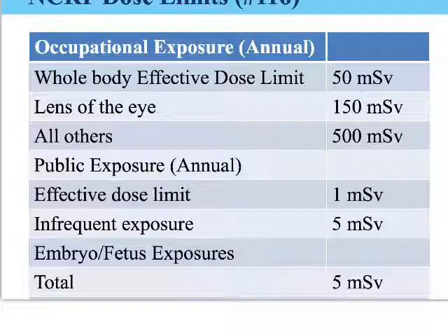Let's talk a little bit about these numbers. So the whole body effective dose limit for anyone who's occupationally exposed to radiation is 50 millisieverts according to the NCRP. Okay, this was a report that came out in the mid-90s. So that's a whole body effective dose. That is what you receive on your radiation badge. For a lifetime? For a single year. That's an annual dose. Okay.